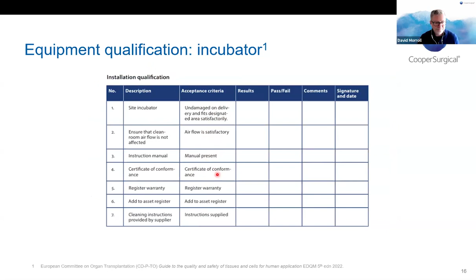So it then sets out what you would do during installation qualification. You can see here it's around: has the equipment arrived undamaged? Is it where it's been put, will that adversely affect clean room airflow if that's relevant? Have you got an instruction manual? Have you got a certificate of conformance? Have you got a warranty? And so on. The operational qualification, this is the bit we get more involved in, I guess.